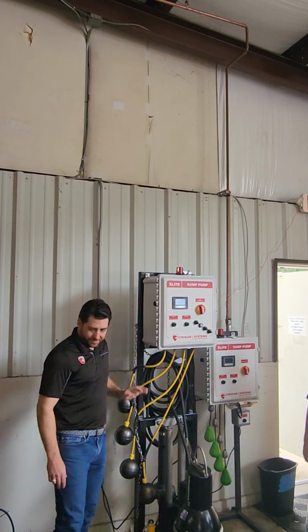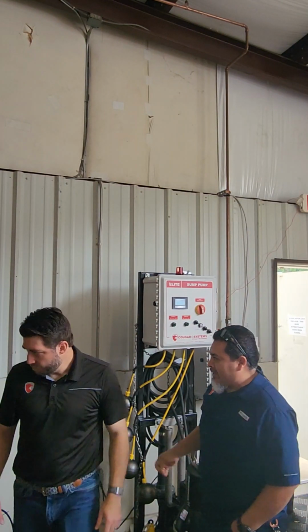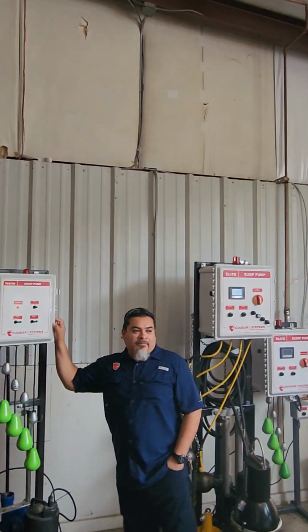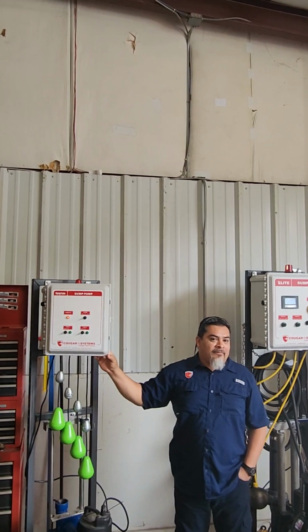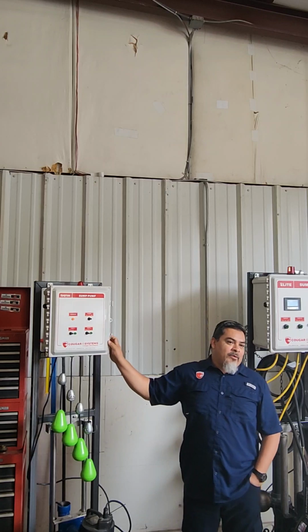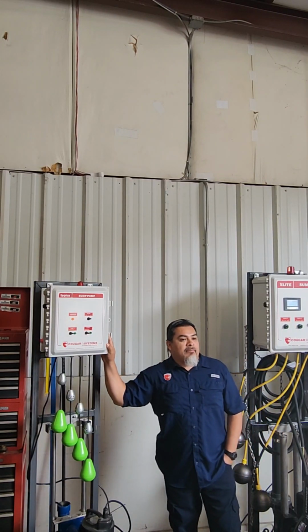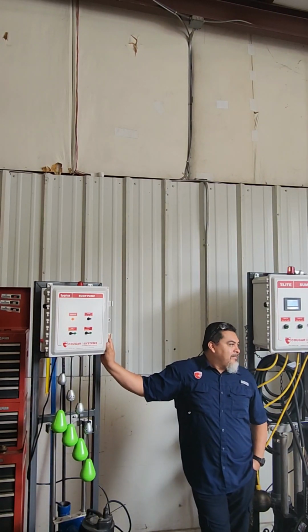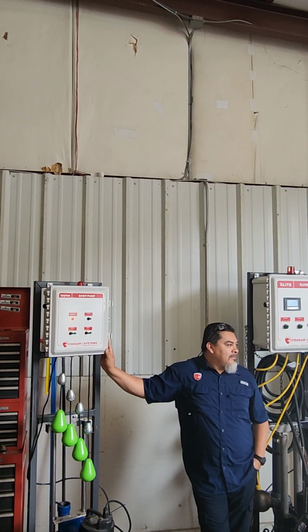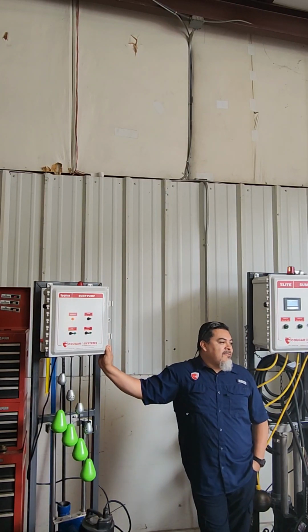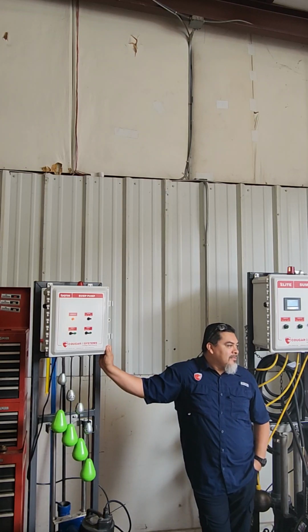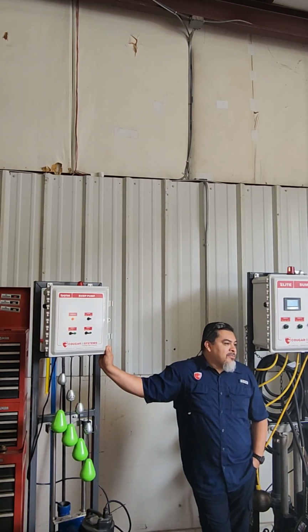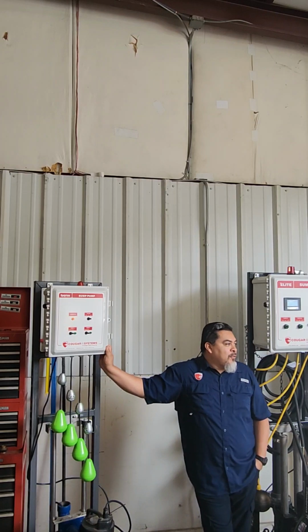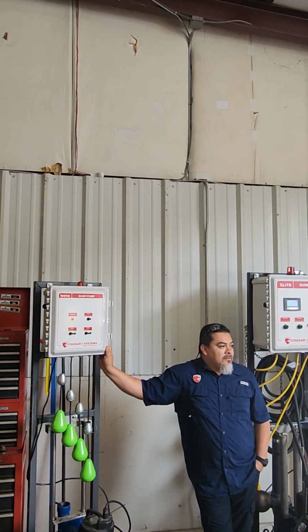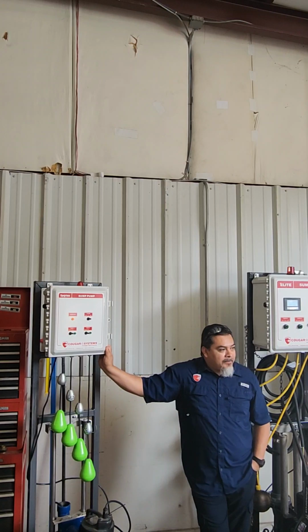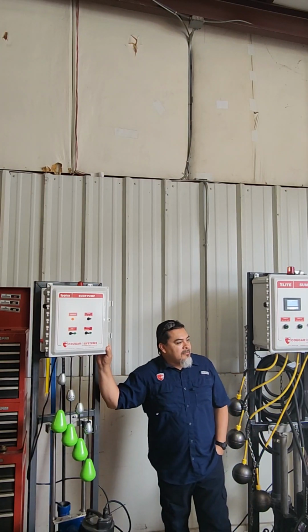I guess what is the most common cause y'all get when y'all go out in the field, when y'all deal with something? Alarm. Floats failing. Floats failing, I mean, but what is the cause? Hey, the pump is not running, the pump ain't working. Normally we don't go out there unless their alarm is on. So what is the most common problem? Floats getting hung up, or the floats aren't set right. Okay, but the pumps aren't coming on. The control's on, but the pump ain't doing anything. It shows the pump being on, but it's not doing anything. And what operates the pump in auto?